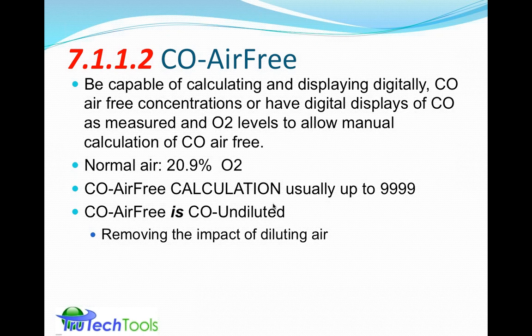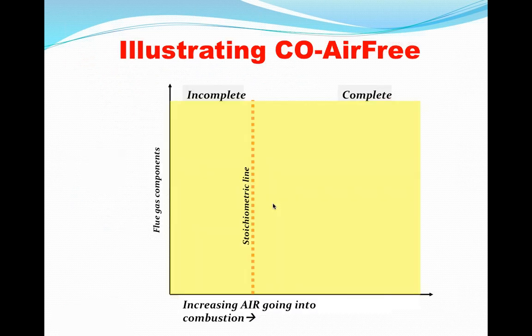CO-AirFree is also called CO undiluted, and basically that's a really good name for it, CO undiluted. It removes the impact of the diluting air. We're going to go over what that means. This comes from our combustion webinar and also the CO-AirFree webinar, but we're going to just do a real quick illustration of CO-AirFree. We have on the left axis the flue gas components in increasing concentration, and then an increasing amount of air going into combustion. Air is a lot of times the gas pedal for combustion. You can vary how much air is going in to impact the rate of combustion.